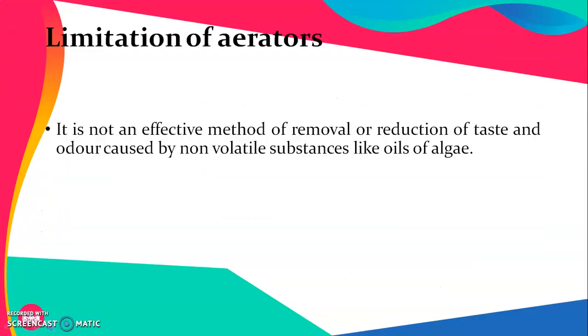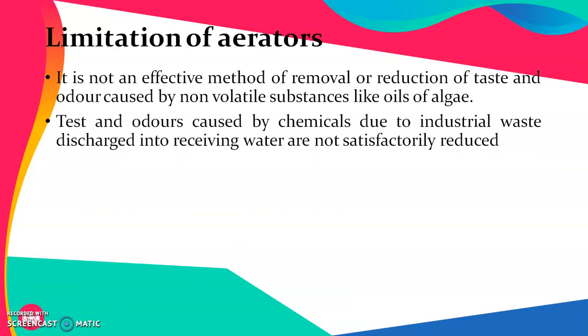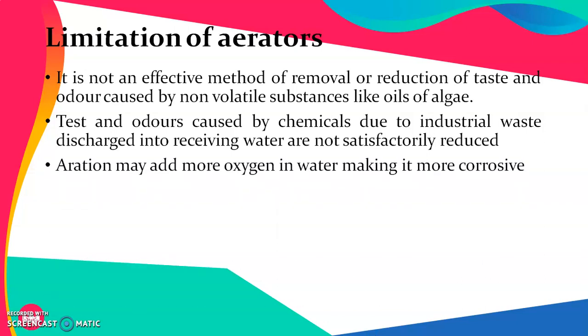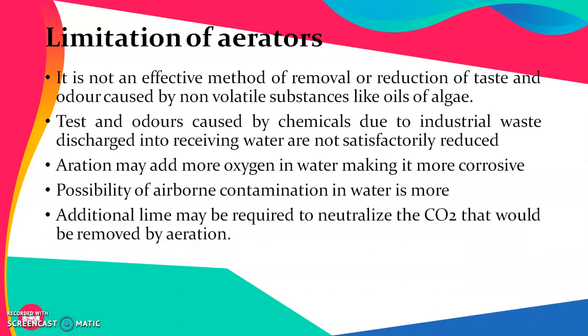The limitation of aerators. The major limitation is that it does not have an effective removal or reduction of taste and odor caused by non-volatile substances like oils or algae. As these are non-volatile, the air is unable to remove the taste caused because of such things. Taste and odors caused by chemicals due to industrial waste discharged into a receiving water are also not satisfactorily reduced. The aeration may in some cases add more oxygen in water, making it more corrosive. The possibility of airborne contamination in water in such a case is more. Additional lime may be required to neutralize the carbon dioxide that would be removed by aeration.